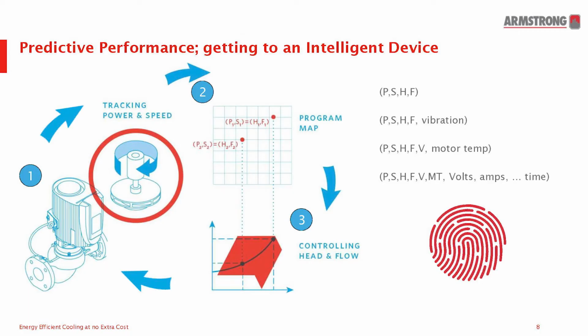That's just the beginning. Beyond that, we can also integrate vibration. With an accelerometer embedded in the device, which can be done on any mechanical rotating device, we can learn things about the device itself if it has damage, and about the environment around it, like if a strainer upstream is clogged and causing cavitation. A lot can be learned by combining vibration information with power, speed, flow, and head.